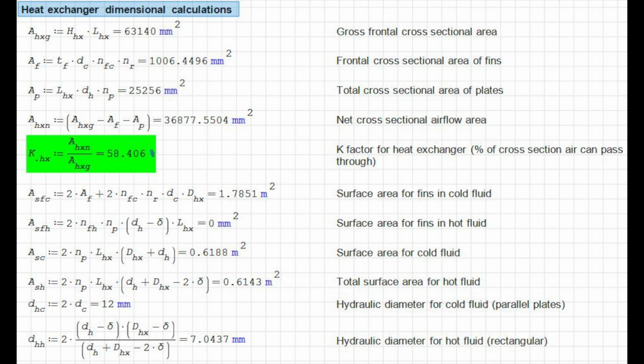Next we need to determine the surface area for the fins in the cold fluid: two times the frontal cross-sectional area plus the rest of the profile of the fins. Next we have the fins in the hot fluid—this one doesn't have any fins in the hot fluid, so it's not considered. This line item is only used for the 19-row dual pass and the 25-row dual pass.